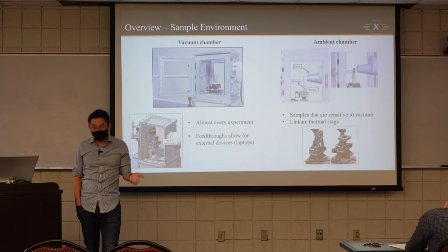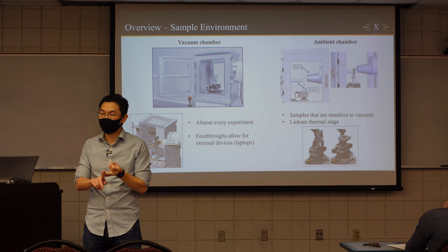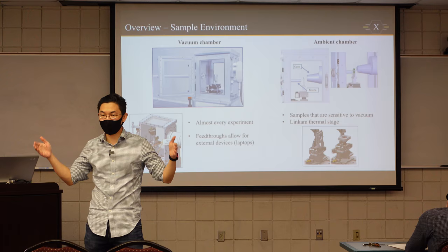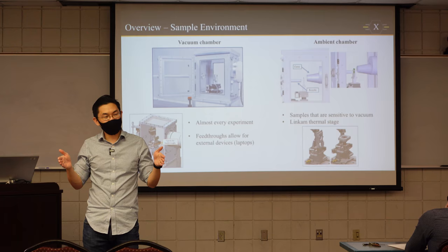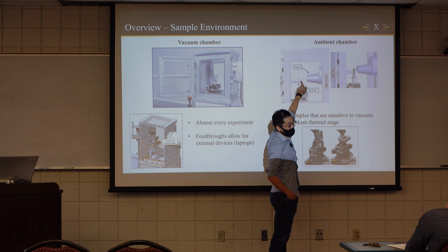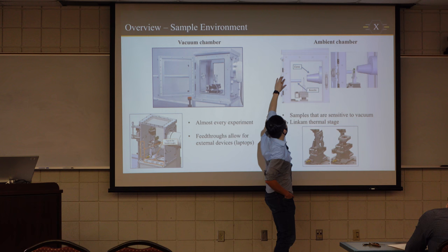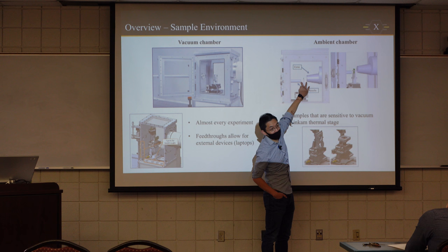Why do we have to do it in vacuum? The simple reason is it can cut down the air scattering. The air has absorption and scattering. It's weak, but it does not mean it's not there, especially when your chamber is fairly long, has 2 feet of air in it. So the other way that we can do is minimize the air gap. So you can leave the sample in air, but you want to minimize it as small as possible. So the second way we can run it is by installing two nozzles and a cone. So this nozzle has a piece of Kapton on the front. And it basically extends the vacuum from the upstream of the mid-line all the way to here. And the bottom part also extends the vacuum from the detector to this basically piece of cone. So you only leave about a few centimeters of air gap in between.